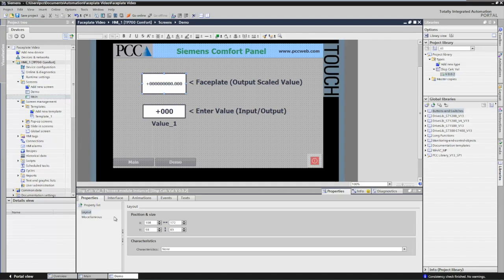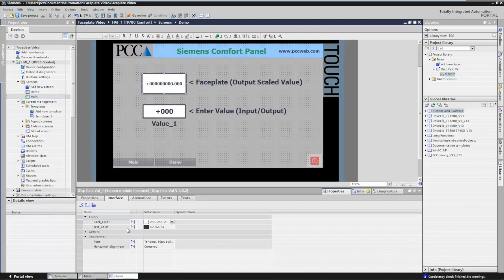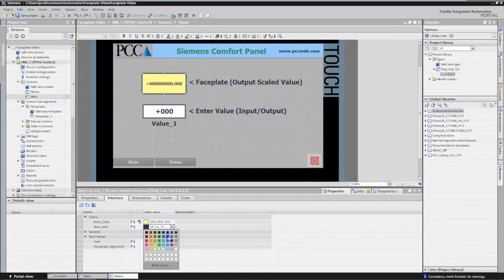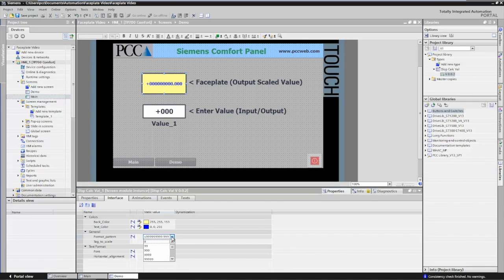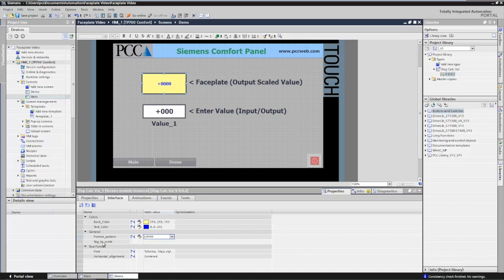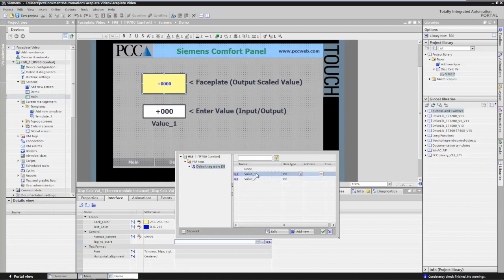Looking at the properties now, you'd think it would be an IO field, but it doesn't have all the typical IO field properties because we created a faceplate. Our user-defined properties are available in the interface area. For the background color, right now it's set to white, but I can change it — maybe yellow. My text color I can change to a bluish color. Under the General area, the format pattern I'll set to display an integer value with four nines. The tag_to_scale, when I click on it, I assign an HMI tag to this property and hit the browse button to select my actual tag or PLC value. The font size I can make bigger, and the justification I'll leave defaulted to center.